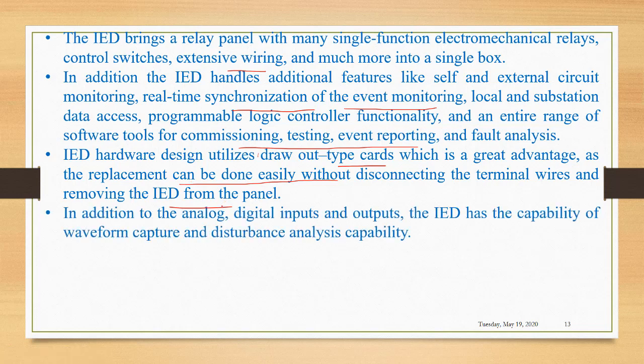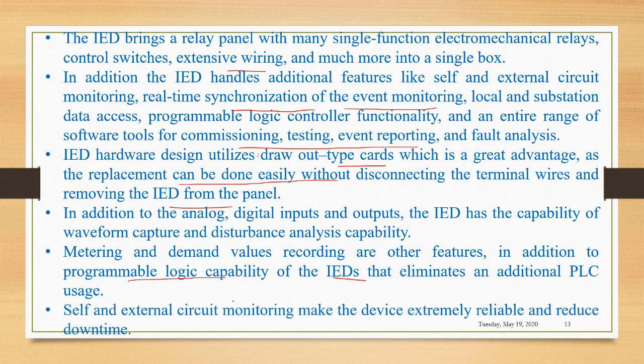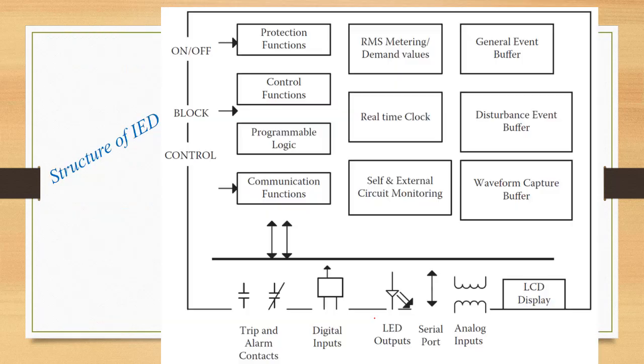In addition to the analog and digital inputs and outputs, the IED has the capability of waveform capture and disturbance analysis. Metering and demand values recording are other features, in addition to the programmable logic capability of the IEDs that eliminates additional PLC usage. Self and external circuit monitoring make the device extremely reliable and reduce downtime.